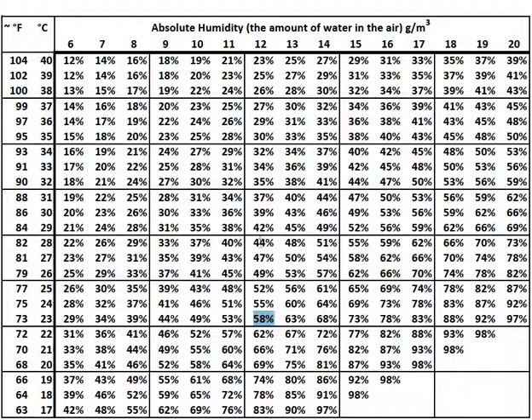But if the humidity is lower than 44% outside, then we've got drier air. When it comes in and cools, it will be drier than the air we currently have in the basement. Of course, if it's more than 44% humidity outside at 82 degrees, then the air will be even more moist than what's currently in the basement, and we'll just end up with things getting even soggier.